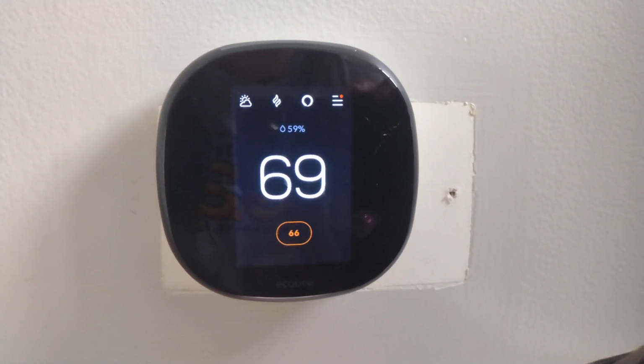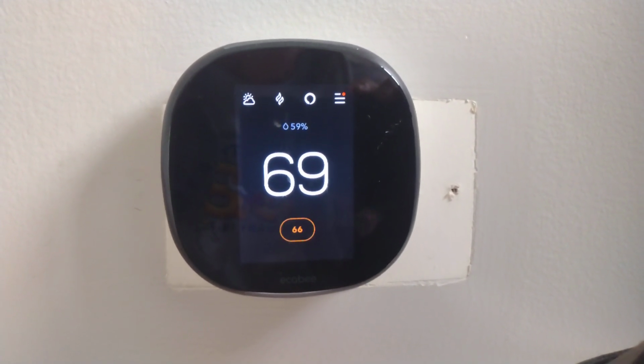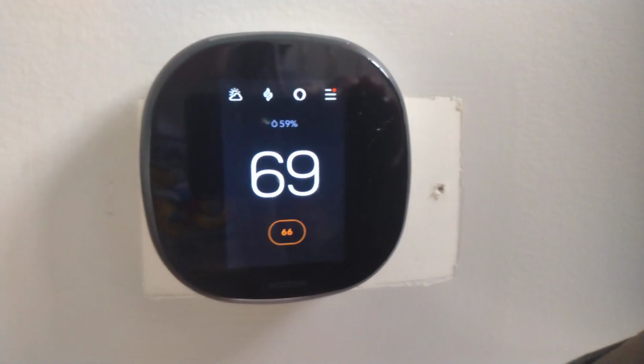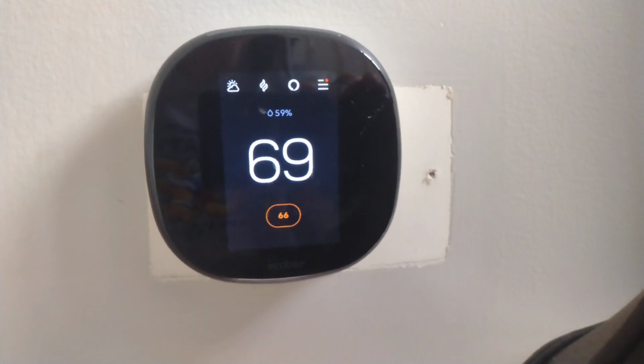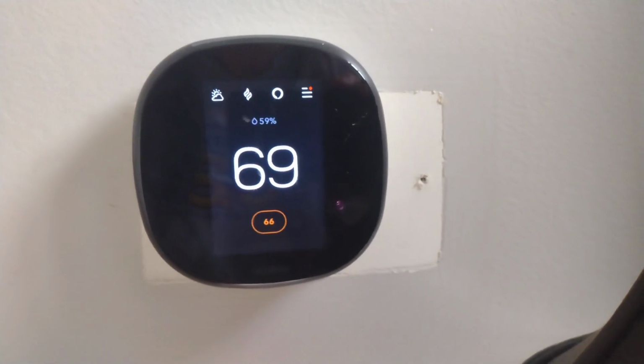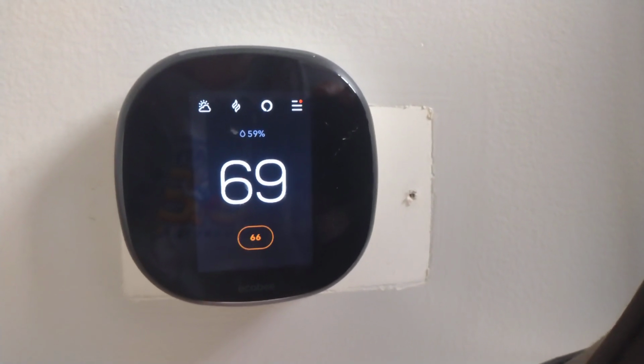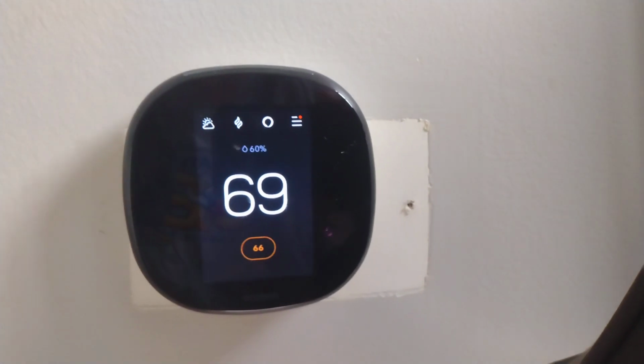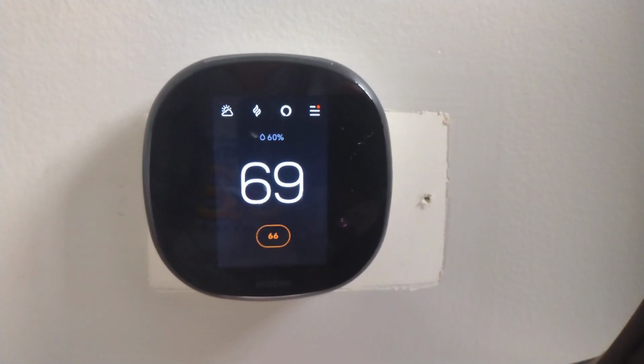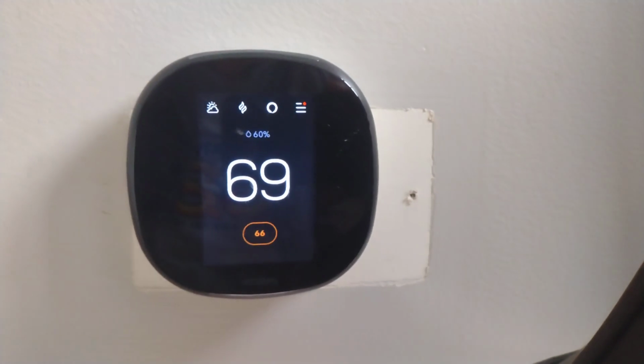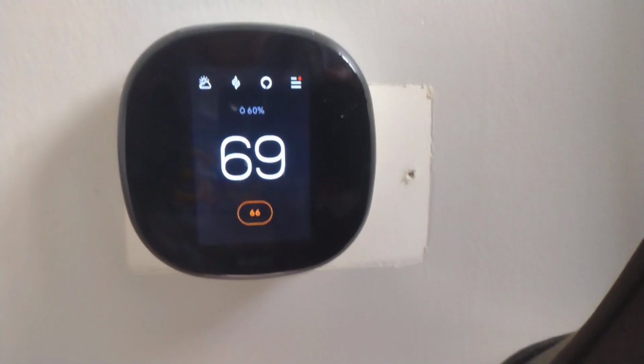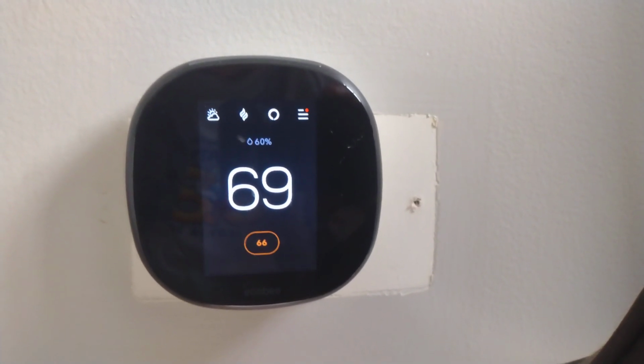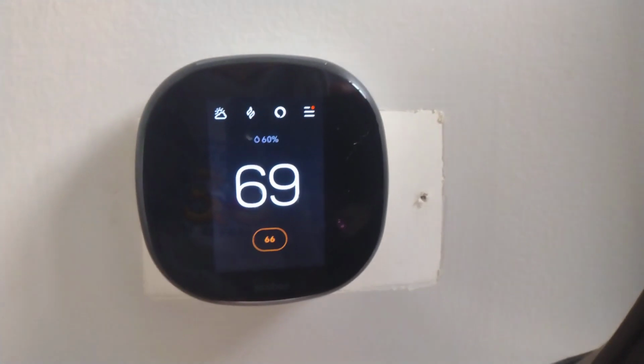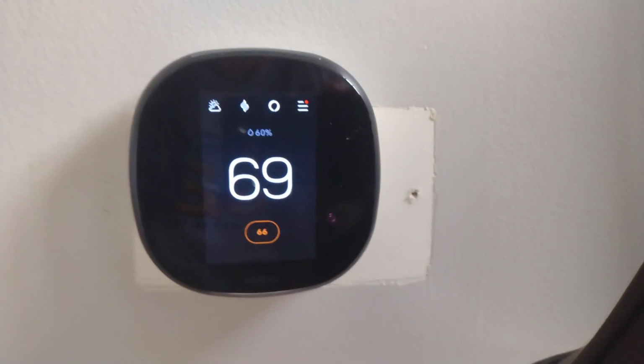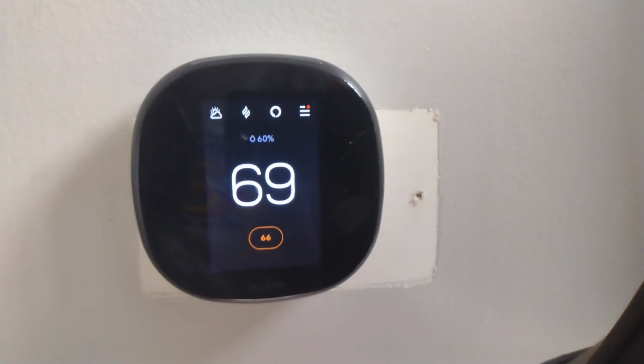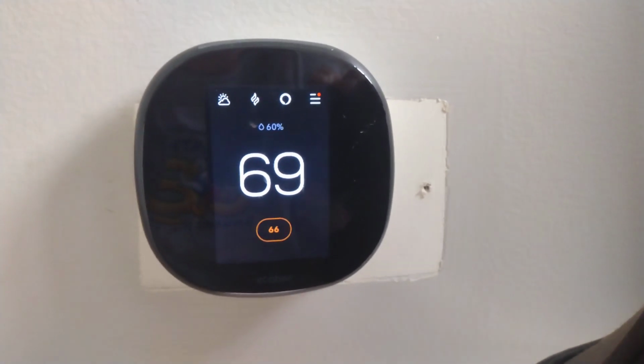We've had this happen to the Ecobee 3 upstairs. It started first periodically shutting off and going dark, and then the Premium, which is brand new, on a 10-year-old air handler, caused the transformer to die, and started doing the same thing where it was intermittently shutting off and on. So by replacing the transformer on both of those units, one was a gas furnace and one was an air handler, that at least for the short term has solved the intermittent power issues.